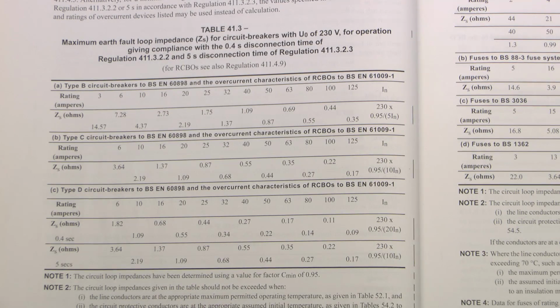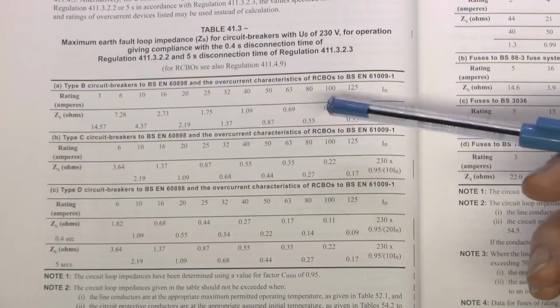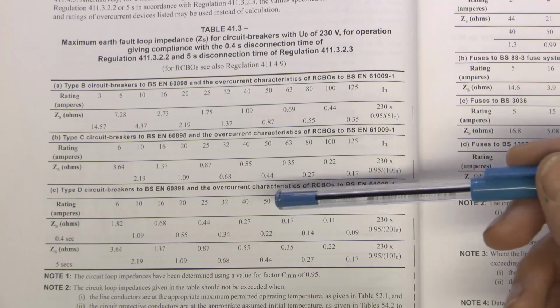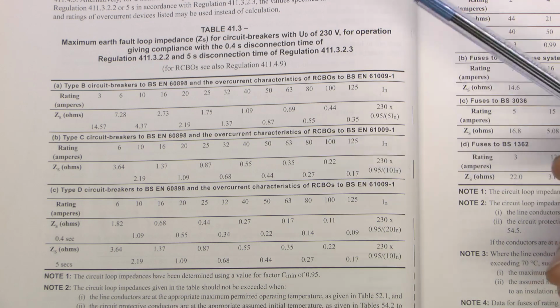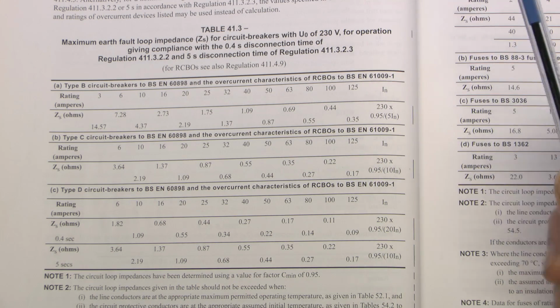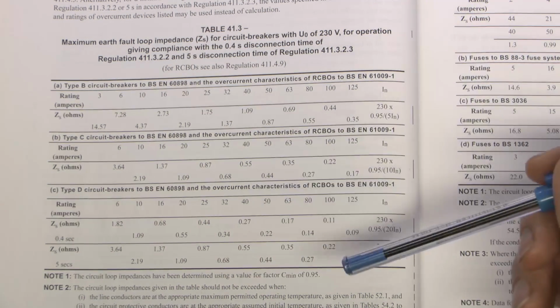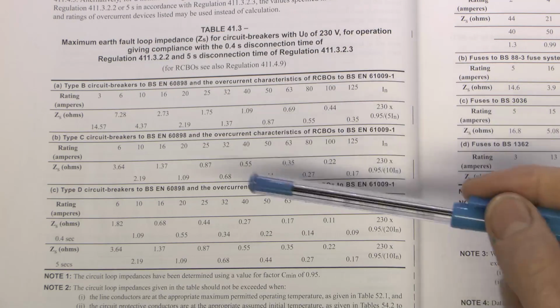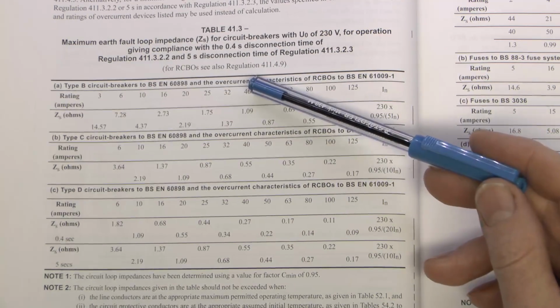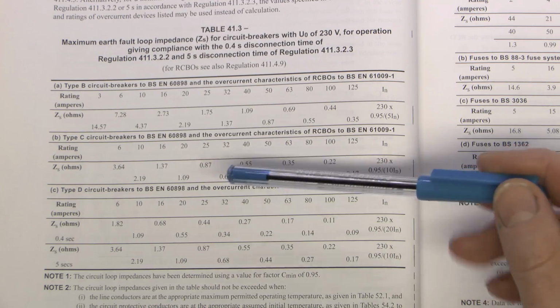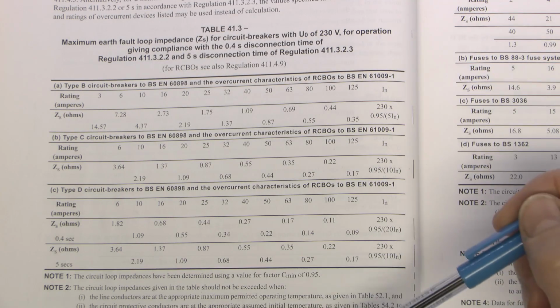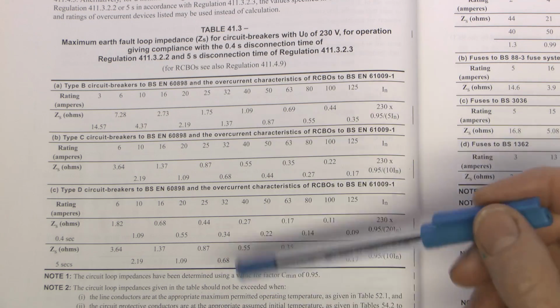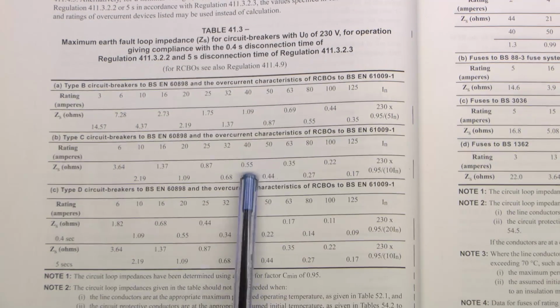values here will apply. And certainly if you consider if you had a TNS type of supply in the UK, the external impedance of those can be anything up to 0.8 ohms. And then of course you have to add on the impedance of the circuit, but even if you had your 0.8 ohms, so you had a 40 amp Type C, your maximum impedance required is actually 0.55. So if you've got a TNS supply and you happen to measure the external impedance to say 0.7, then it's pretty much game over for the Type C, because the maximum is 0.55.